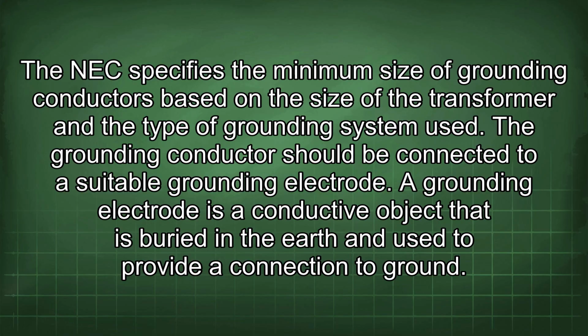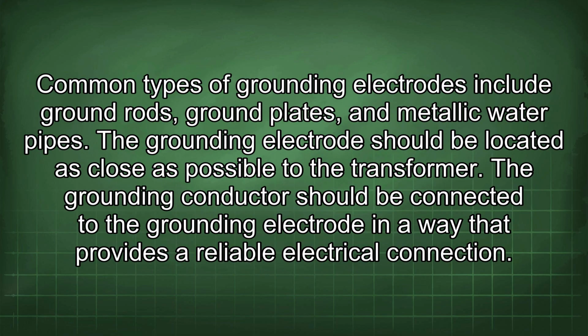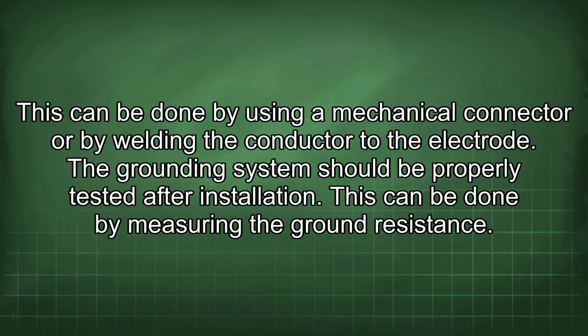A grounding electrode is a conductive object that is buried in the earth and used to provide a connection to ground. Common types of grounding electrodes include ground rods, ground plates, and metallic water pipes. The grounding electrode should be located as close as possible to the transformer. The grounding conductor should be connected to the grounding electrode in a way that provides a reliable electrical connection. This can be done by using a mechanical connector or by welding the conductor to the electrode.